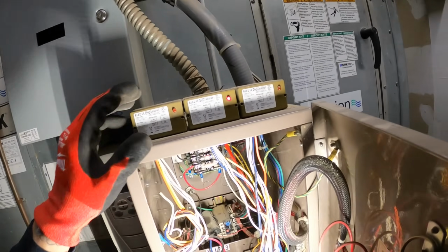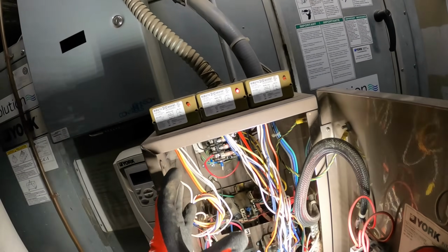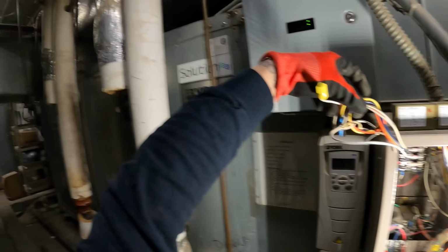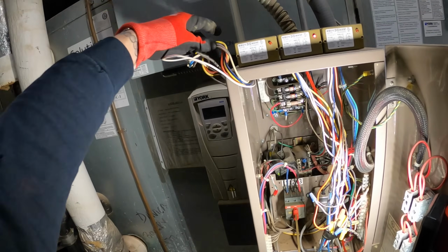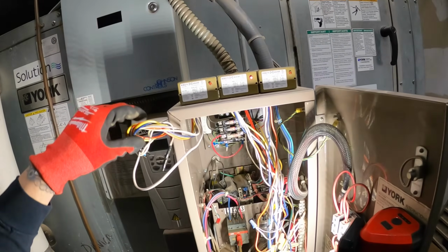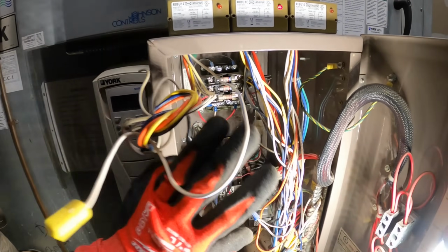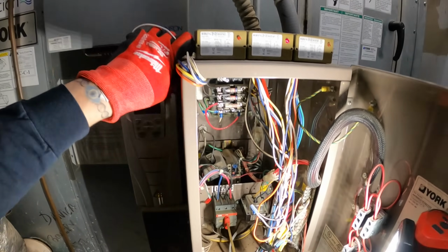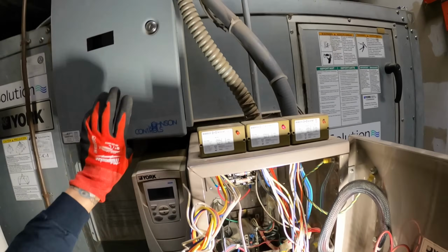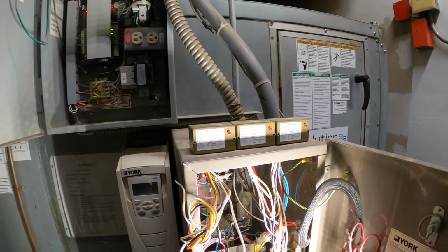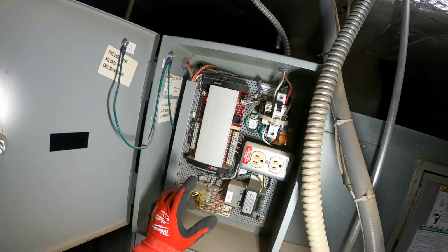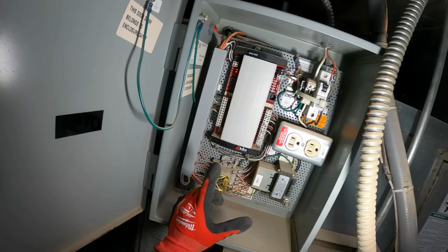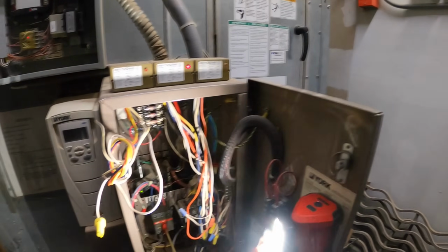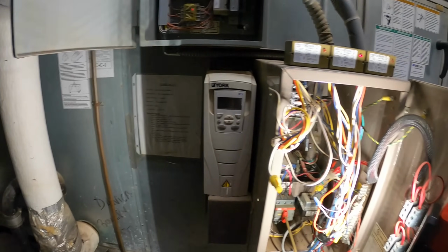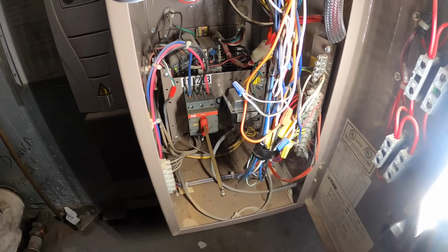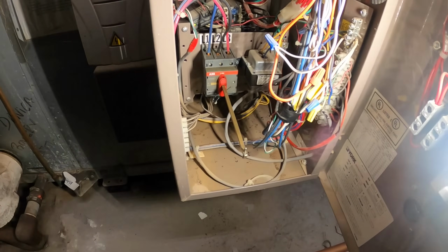We don't have power on this relay. Oh wow. Well, I'll tell you why we don't have power for that relay. Look, Chris, there's no control. This thing is not even wired. So we can get that out of the equation. So that wouldn't light up regardless. So somewhere through this control, the fan would turn on through their system. I don't know how it's wired exactly, but it has to go through that.